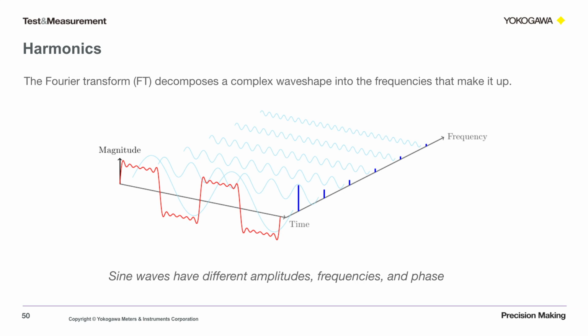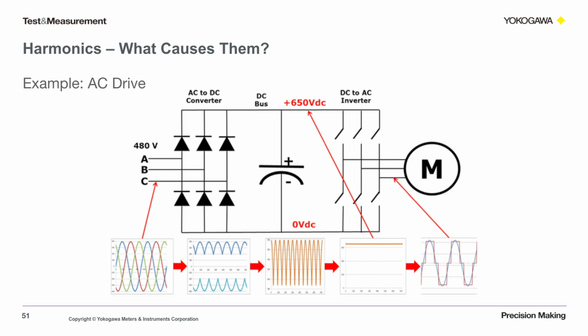By applying a Fourier transform, we can break down a complex waveform into its basic components, which turn out to be sine waves at different frequencies, amplitudes, and phases. The fundamental waveform can be called the first harmonic waveform. The second harmonic has a frequency twice that of the fundamental. The third harmonic has a frequency 3 times the fundamental, and so forth. In this example, the square wave has only odd harmonics, for a reason we're not going to get into in this webinar. Harmonics have been around over the past decade since the introduction of electric drives for motors, fans and pumps, and power supply switching circuits such as the rectifiers shown here. This is part of a motor controller or an AC drive.